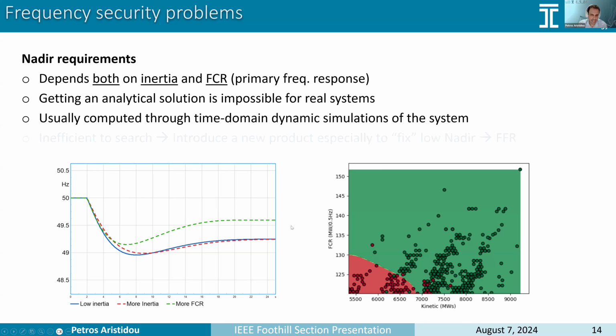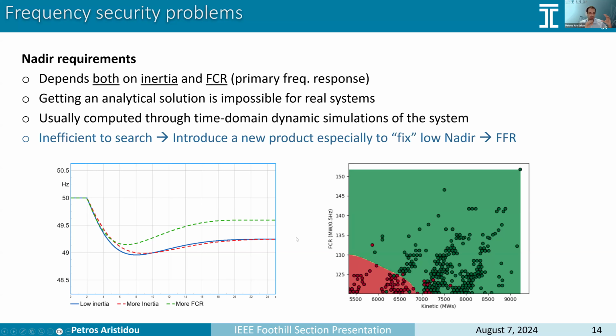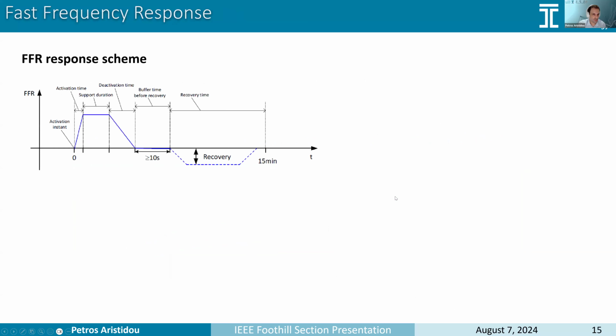Now, it is very challenging to find the best combination of inertia and frequency containment reserves in order to comply with all these requirements and the nadir requirements and be most economical. So in most countries, including Cyprus, system operators have introduced new products, which are named fast frequency response products. The main purpose of these products is to fix these low nadirs without touching the committed inertia or the frequency containment reserves. There are different solutions in implementing this fast frequency response.